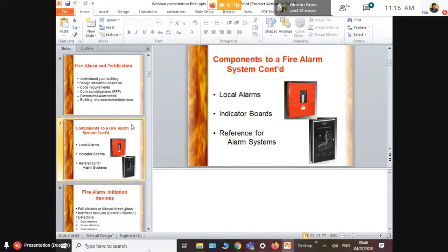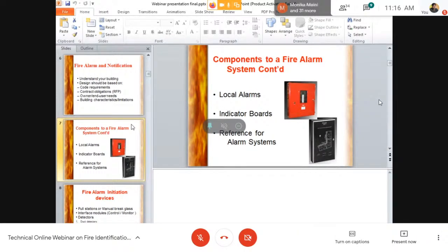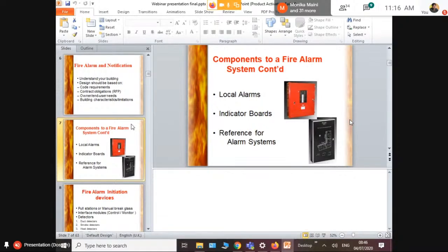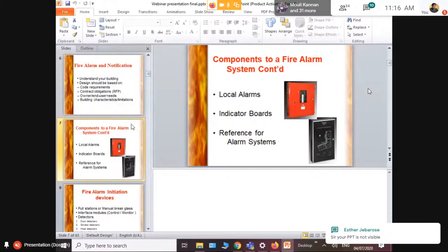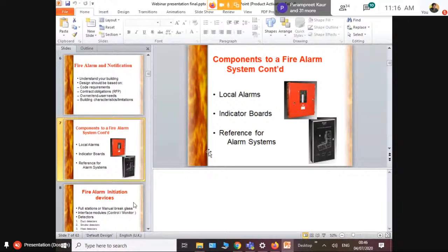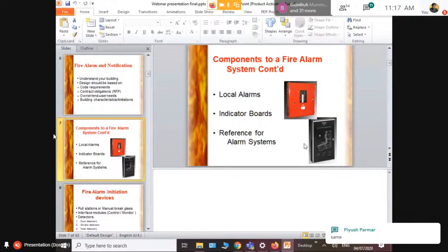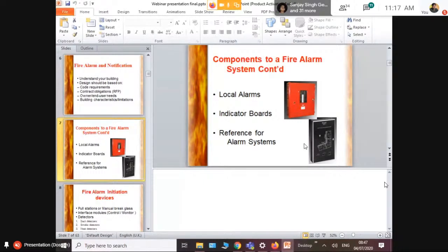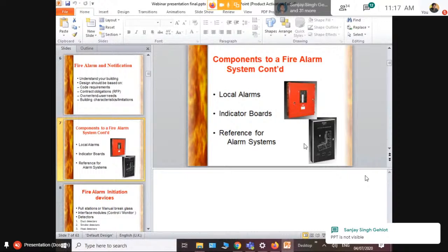Indicator boards can be the main control panel or any sub panel or even a mimic panel, which will show you where a fire has occurred or where a fire condition has occurred. The reference for the alarm systems is a notification which can be given in zone separations. Like if you have a building of 20 floors, you will notice a fire in one of the areas, but you will not know it specifically. So in each floor, or in separations of 3 or 4 floors, you will have indication boards where you can see the exact zone where there's a fire. So that is how it is.